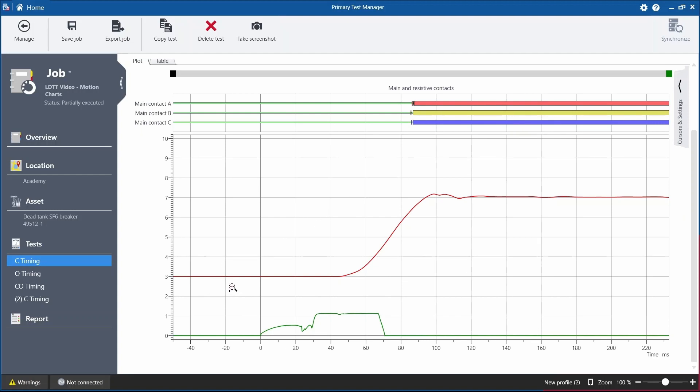Below that, we have our travel curve, which is showing how the contacts are traveling through from one position to the final resting position. And at the bottom, we have our coil current, which is the current that's being induced in the close coil for this measurement.